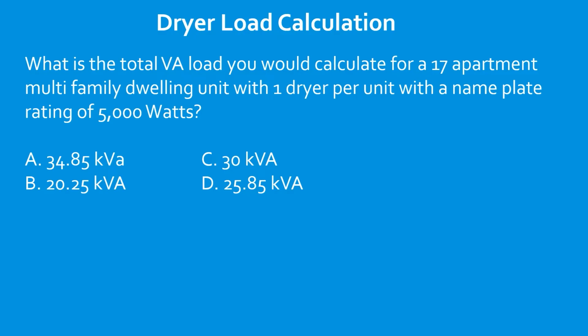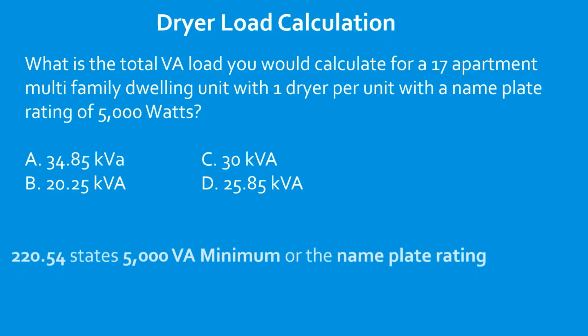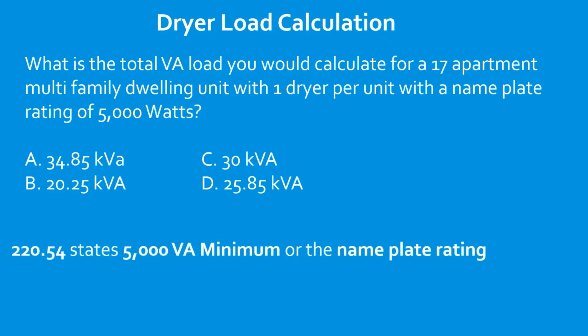Great job. What is the total VA load you would calculate for a 17 apartment multifamily dwelling unit that has 1 dryer per unit with a nameplate rating of 5,000 watts? This one's a little bit more complicated, but we'll go through the same motions. We're going to use Article 220.54, and it states that we have a 5,000 VA minimum or the nameplate rating. You may see me repeating things over and over because I want to beat it into your brain, okay? 5,000 minimum or the nameplate rating.